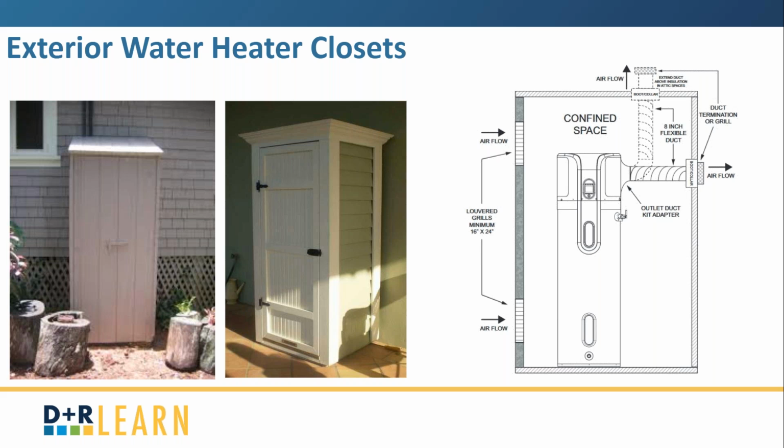Okay. Yeah. So it has to have those ambient temperatures to be able to function properly. And the warmer they are, the more efficient. So you'll have some impact financially, even if you're operating it in the garage 12 months out of the year, but the temperatures are hovering around 40 degrees inside that garage. It's not gonna be as efficient if it were drawing 70-degree air, for example. But it's still gonna be beating the heck out of your electric water heater options. We talked about 300 to 400% efficiency. You could actually get down to 275% efficiency, even 250% efficiency, and you're still going to see some savings.